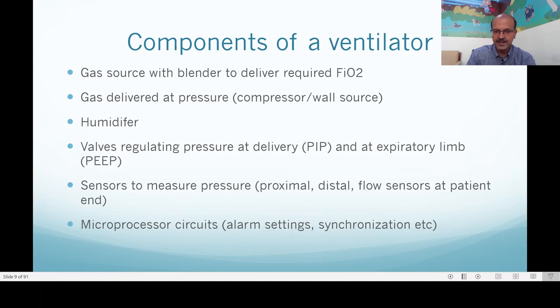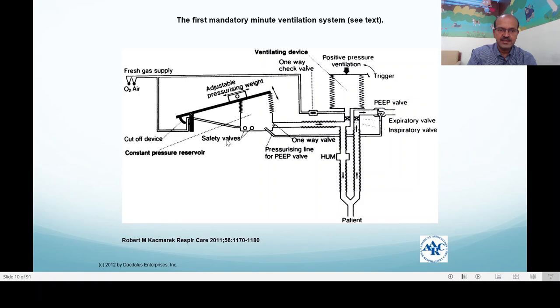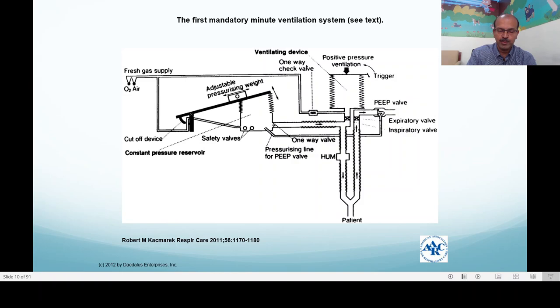Regarding synchronization: gas supply comes in through the valves, positive pressure ventilation happens depending on the trigger, it goes to the patient after humidification, and the PEEP valve provides resistance to expiration creating positive end-expiratory pressure. There are safety mechanisms including alarm limits and safety valves. We have great advances in humidification as well — circuits help avoid water logging as humidity increases in the inspired air. There are tubings which absorb or evaporate water, and we have heater wire circuits as well.